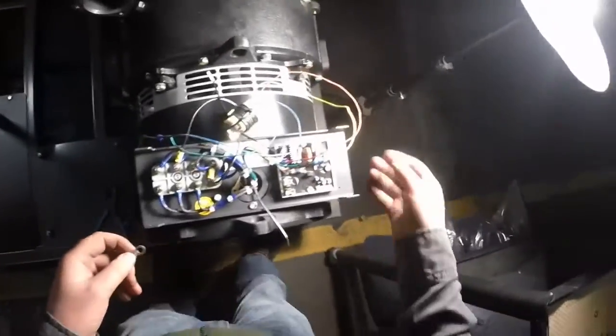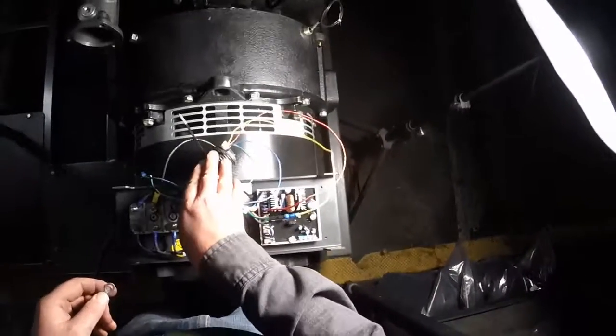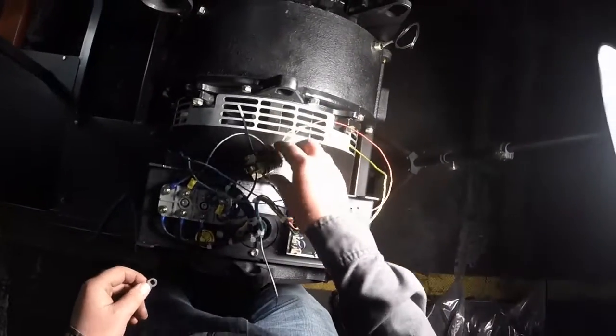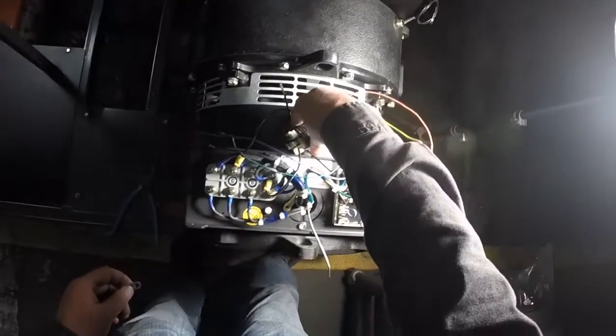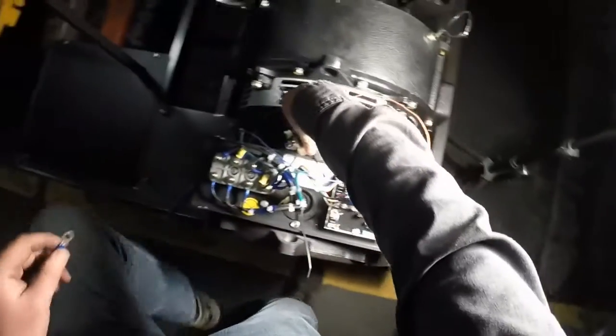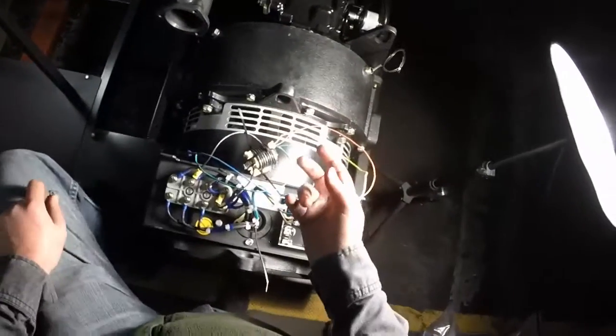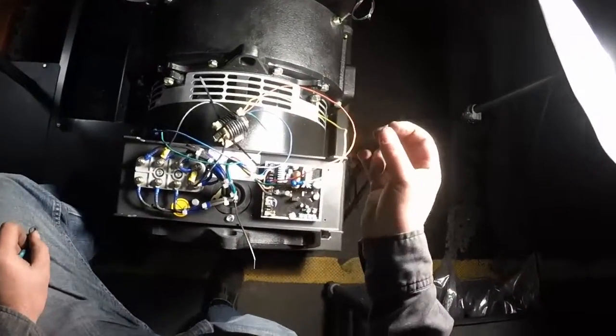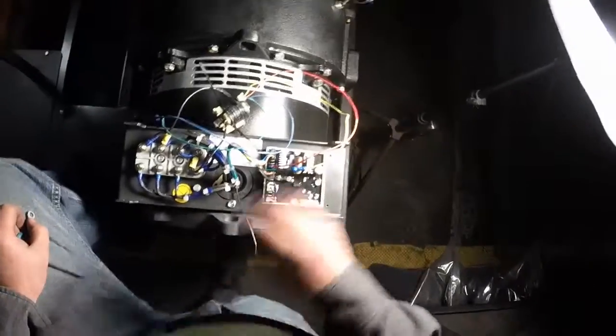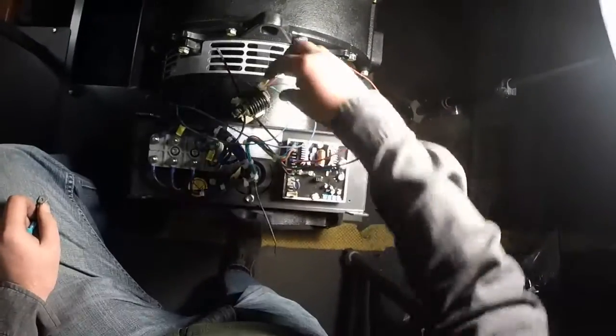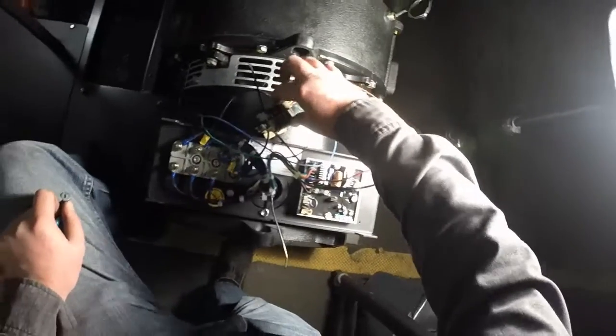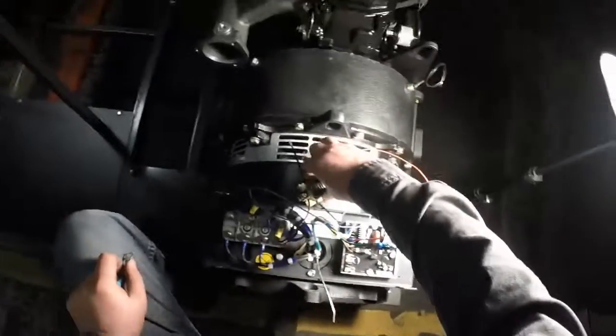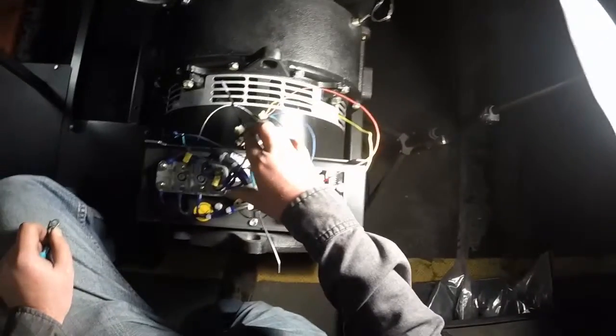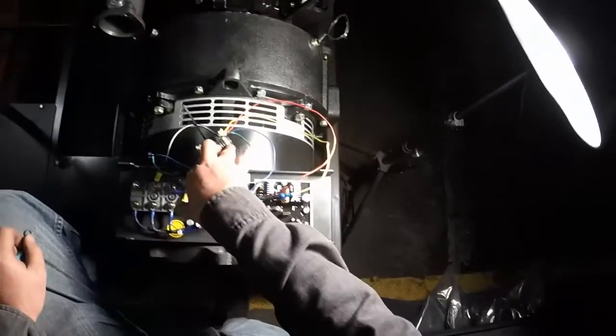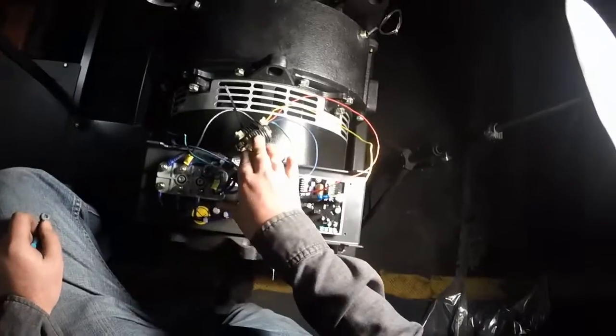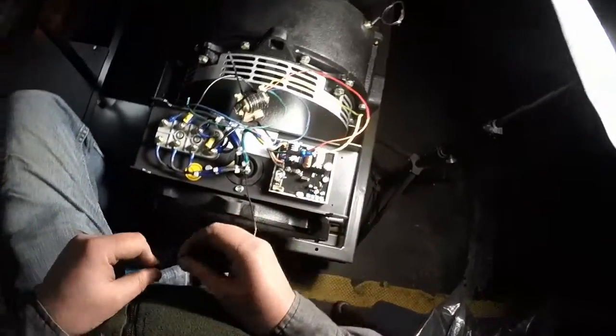As I said before, the polarity of current transformers is critical. If they are wired incorrectly, since we're trying to dampen the reactive power, if the polarity is flipped, you could end up getting a very rapid increase in current flow. And we've seen when this is flipped around and we try to do load sharing, we get a near immediate short circuit alarm on the DeepSea. So we want to avoid that and want to make sure that every generator is connected correctly.